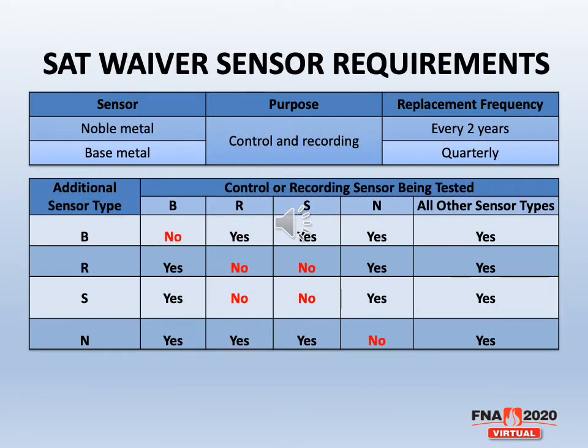As you can see from the table supplied here, again, your sensors, if they're noble metal and you're using them as control and recording sensors, those will have to be replaced every 2 years. And if you're using base metal thermocouples at control and recording, those would have to be replaced on a quarterly basis. Also, there are different sensor types that have to be used for your comparison check. So if your control sensor is type S, you would be able to use a type N or type B sensor. You wouldn't be able to use a type R since the dissimilar metals in the constituents of those thermocouples. So this table here shows you what your additional sensor must be to do your weekly comparison checks against.